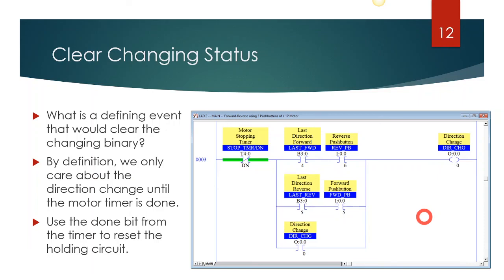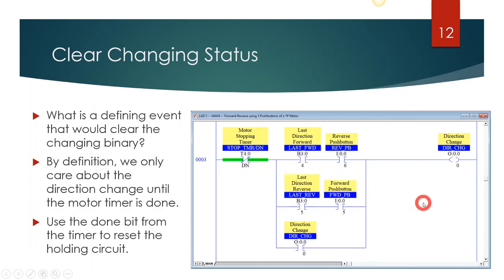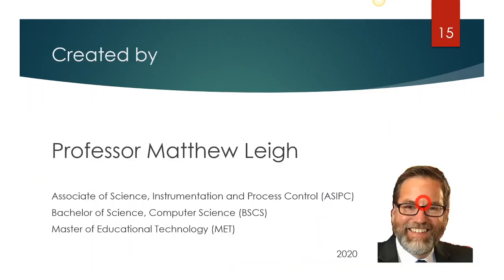A couple of things you'll need to add to your program: first, write the code for remembering the last reverse direction; and second, use the direction-change bit to disable either your forward or reverse direction from being able to change during a direction change. This lesson was based on three push buttons — if you're using a selector switch, just substitute the selector switch addresses instead of the push button addresses. That's the difference between this job and the next job.